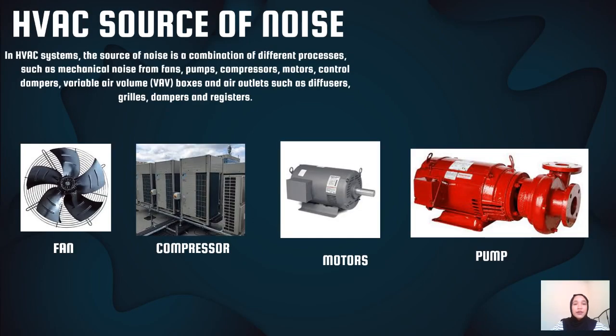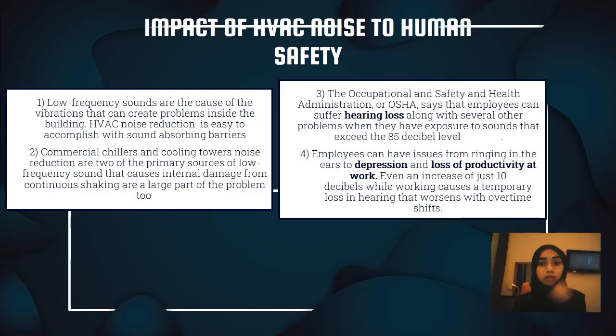Next is the HVAC source of noise. In an HVAC system, the source of noise is a combination of different processes such as mechanical noise from fans, pumps, compressors, motors, control dampers, variable air volume boxes and air outlets such as diffusers, grills, dampers and registers.